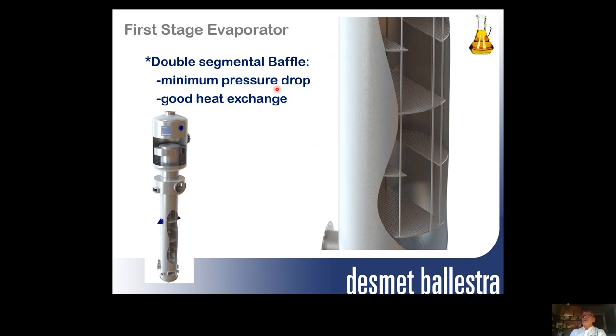As mentioned before, the concentration outward from this equipment is up to 90% oil. The gases inside use what we call double segmental baffles — not one window, but two: one big central window, then two on the next set of baffles, and central again on the next. So there is a minimum pressure drop; the gas path is quite straightforward but not a big pressure drop, which could generate safety concerns in the entire plant.